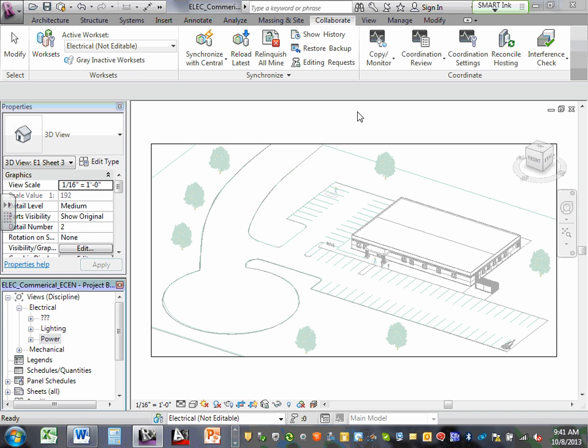You have to pay attention to that third dimension. So when you start dropping your receptacle and it doesn't show up, that's because your receptacle is not placed at the right height. Luckily, all receptacles and lights come with a default. A project like the commercial project we're going to do is easy — it's a one-story project. When you drop a receptacle, it comes at a default of about a foot and a half from the ground and you can see it. But in a multi-story building, if you're not setting your system right, that light might not show up because it showed up in the ceiling above it.